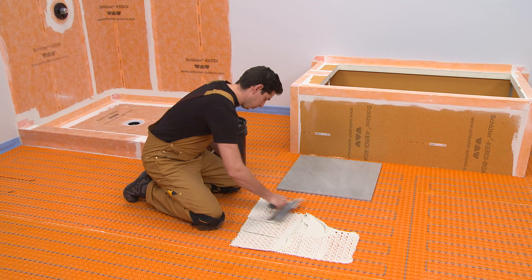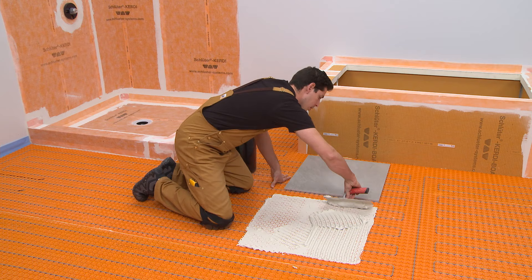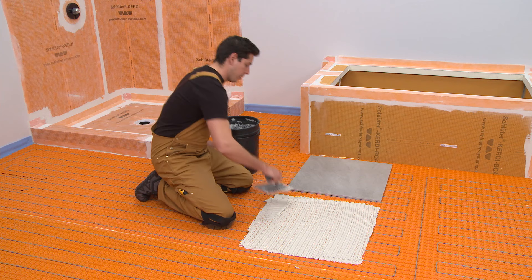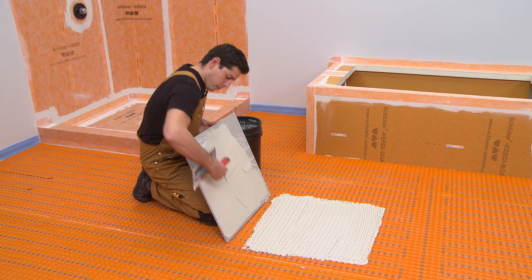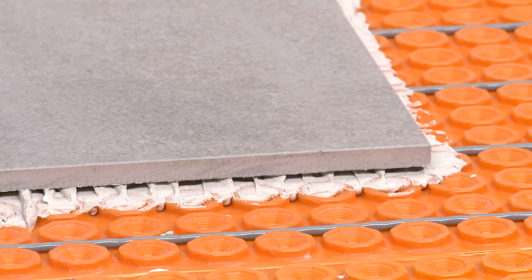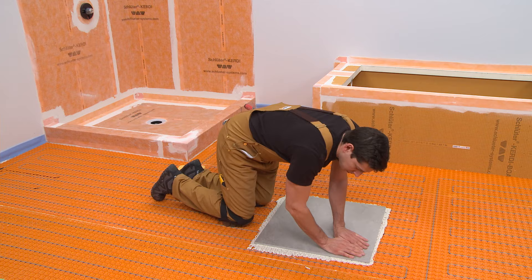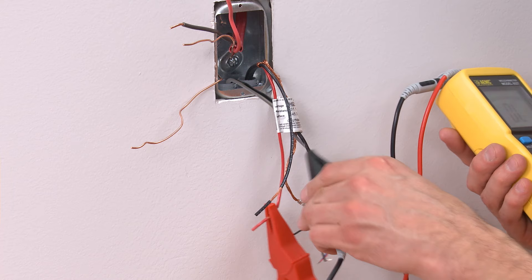Tile is installed over DITRA-HEAT and DITRA-HEAT DUO using any Schluter thin-set mortar or unmodified thin-set mortar. Fill the matting with thin-set mortar and comb additional mortar over the matting using a trowel appropriate for the size of the tile. While the heating cable is protected by the matting, be careful when applying the mortar not to damage the cable with the notched trowel. Back-buttering large-format tiles is a useful way to help ensure proper coverage. Solidly embed the tiles in the setting material, making sure to observe the open time of the mortar. Repeat the heating cable and floor temperature sensor tests to verify the cable was not damaged during waterproofing and/or tile installation.